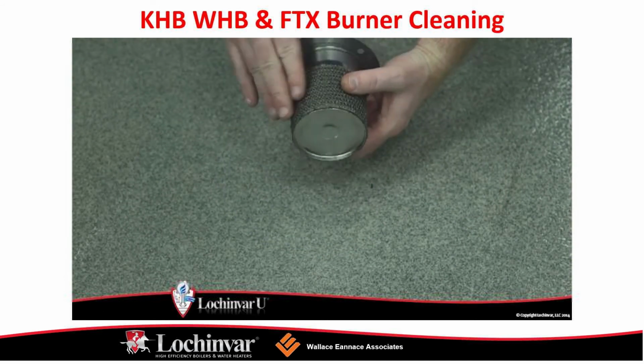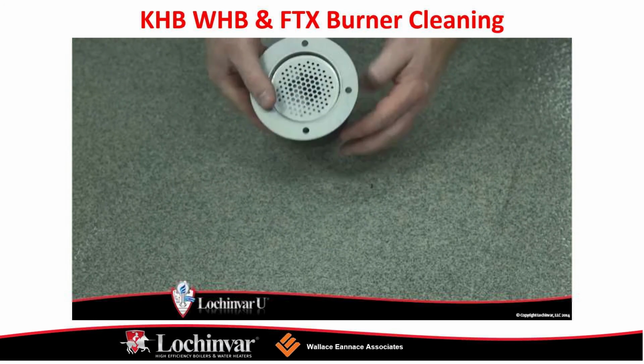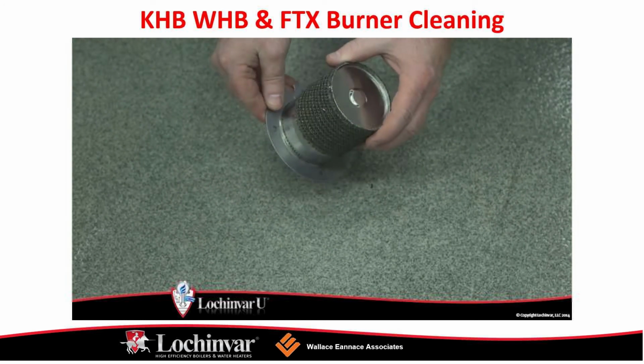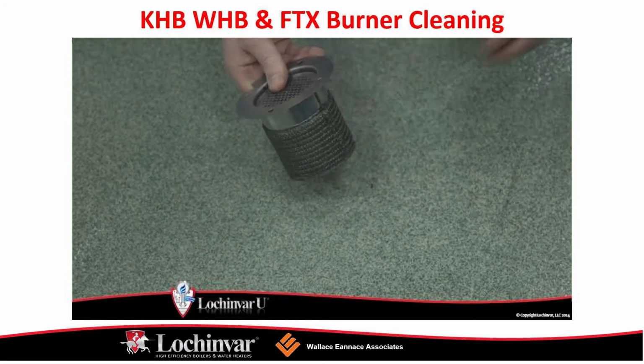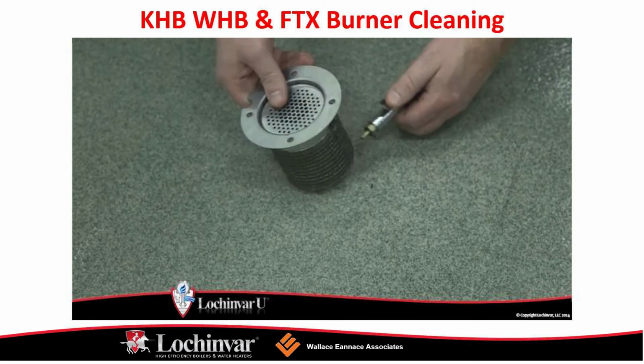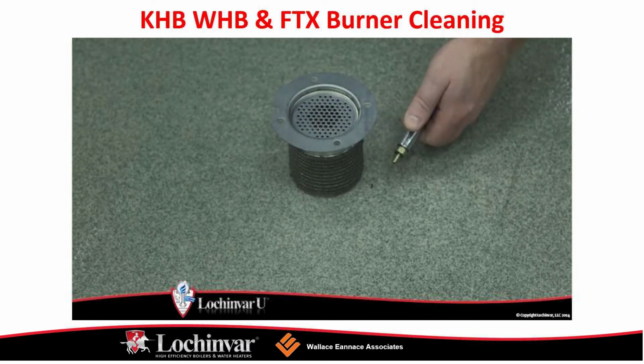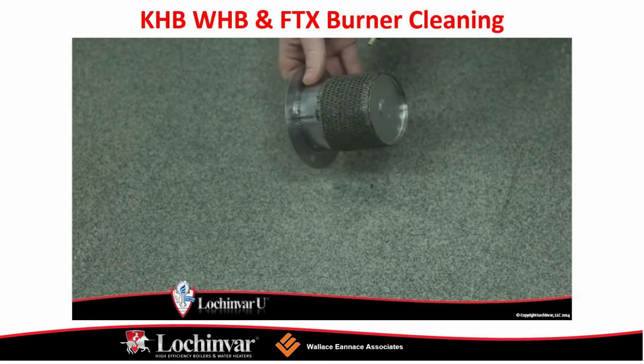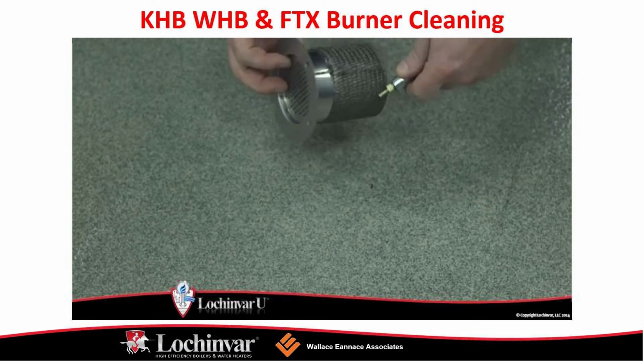And carefully remove the heat exchanger door. A gasket is used to seal between the heat exchanger door and the heat exchanger. Care must be taken not to tear or damage a gasket. If a gasket is damaged or torn, then it must be replaced.